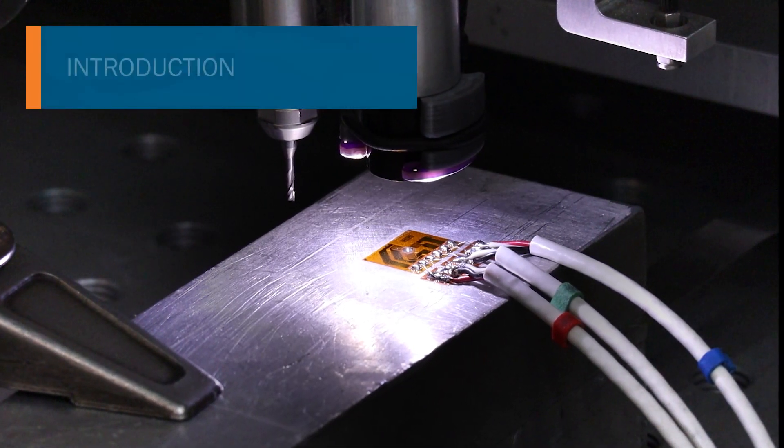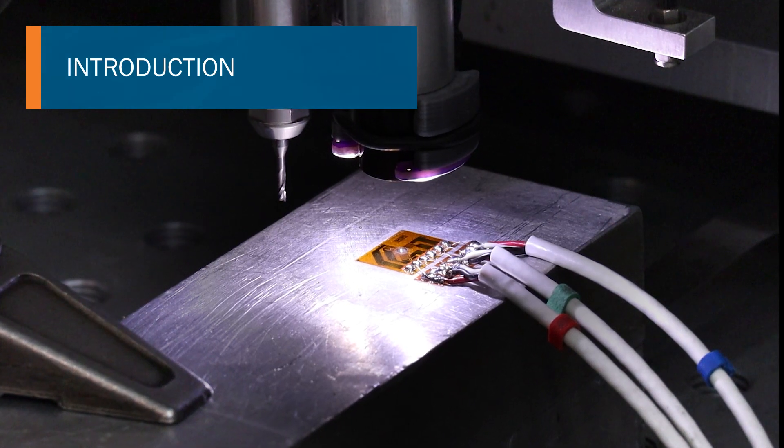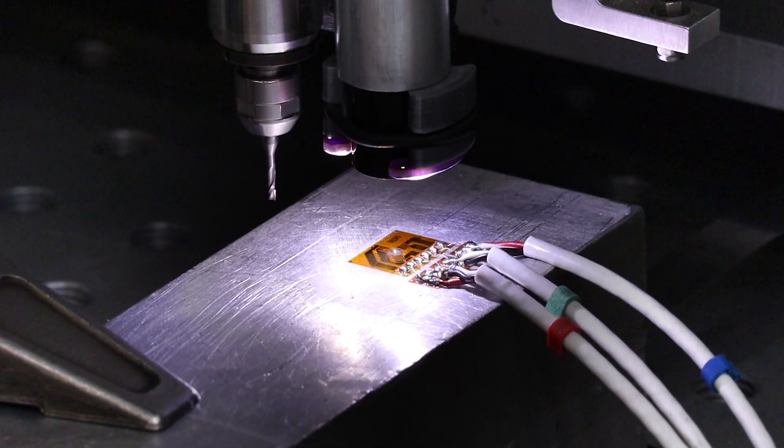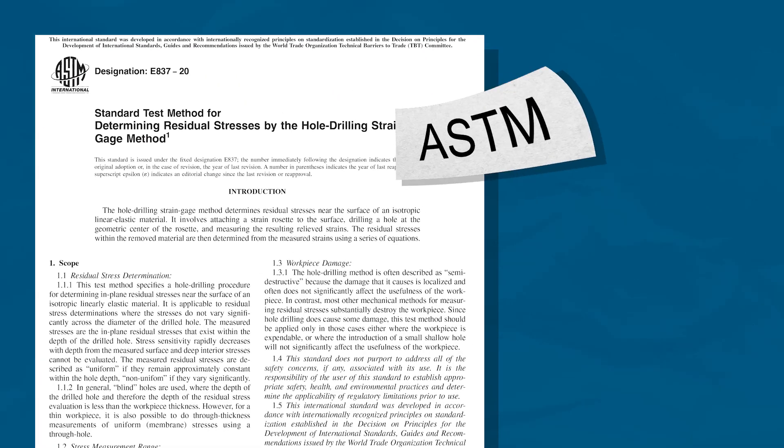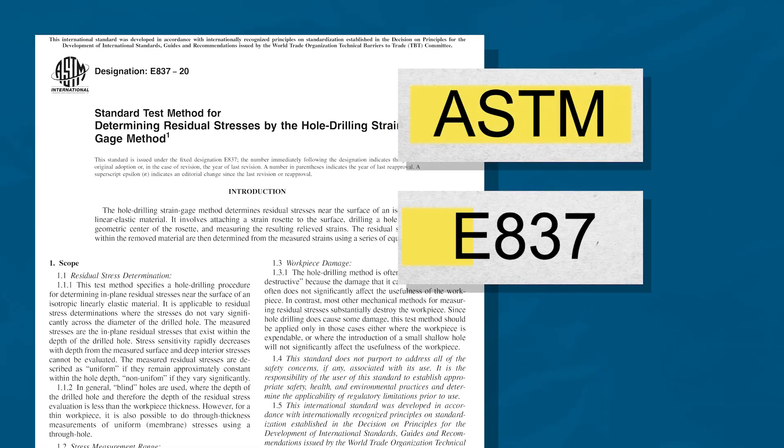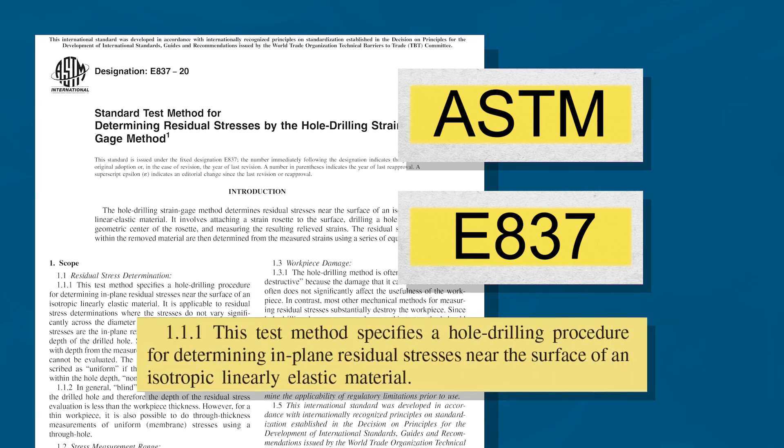Hole drilling is a near-surface residual stress measurement technique in which a small hole is drilled into the surface of a test specimen. Standardized by ASTM as E837, hole drilling is typically performed by drilling small depth increments until a final depth is achieved.